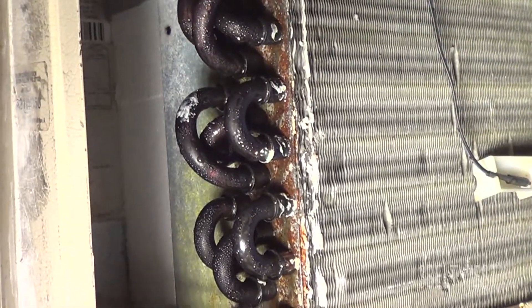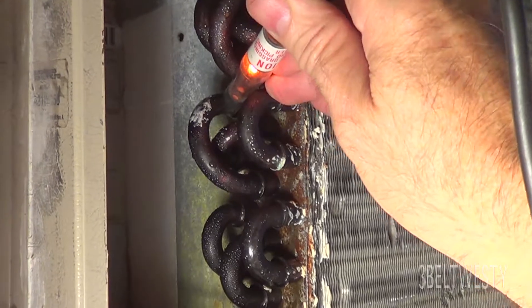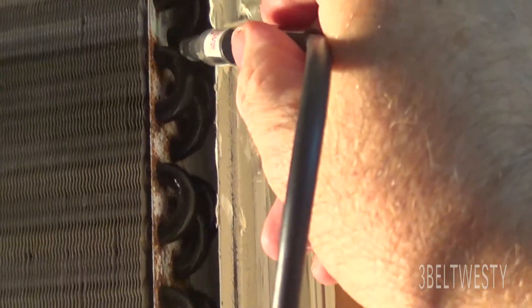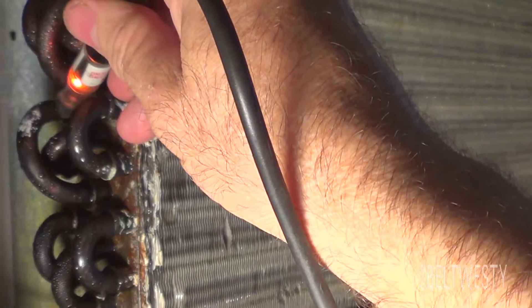You spray on it and you really can't see anything, but it screams. That's the H10 halogen leak detector. Go over here on the other side, strobe it down — there's nothing. You can also tell it's fairly clean. And there's the bad tube.